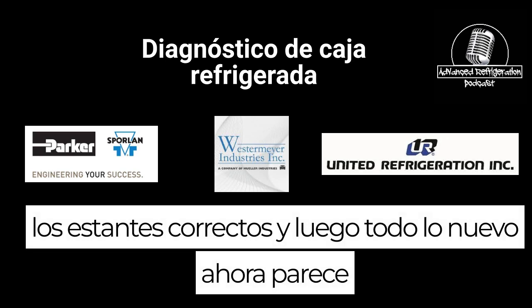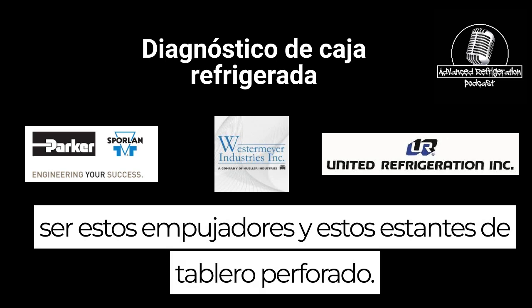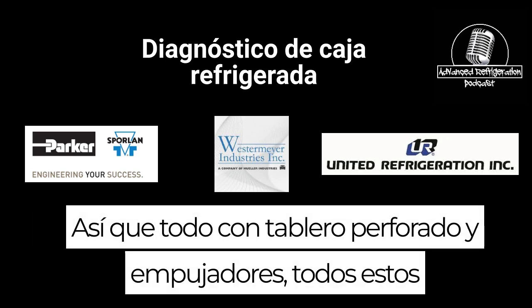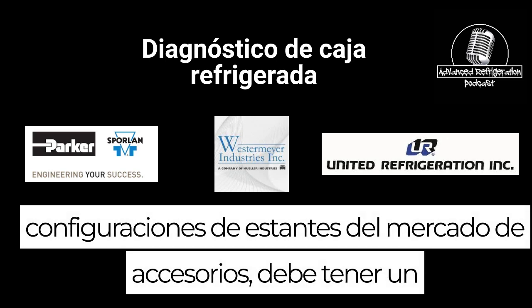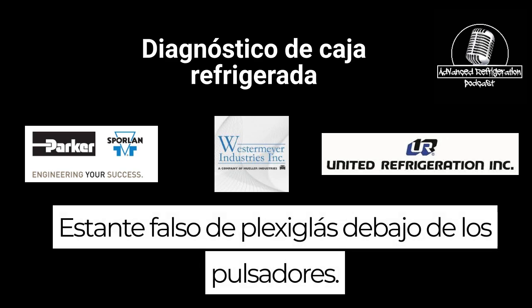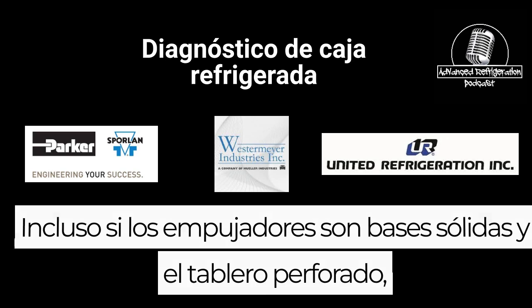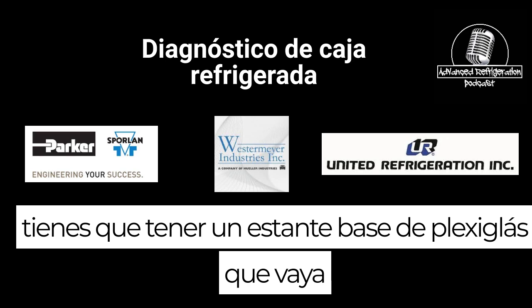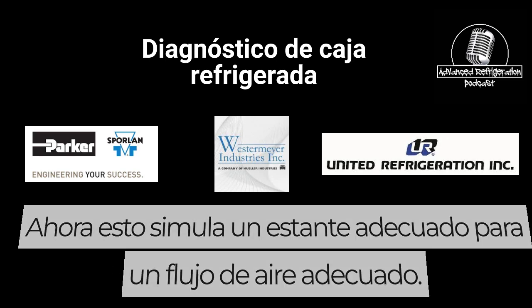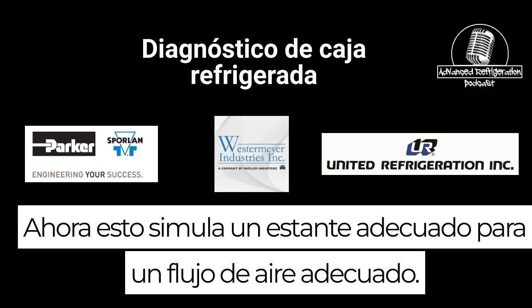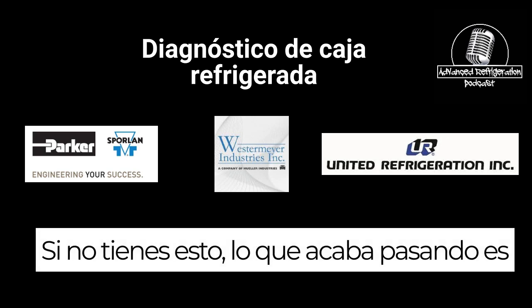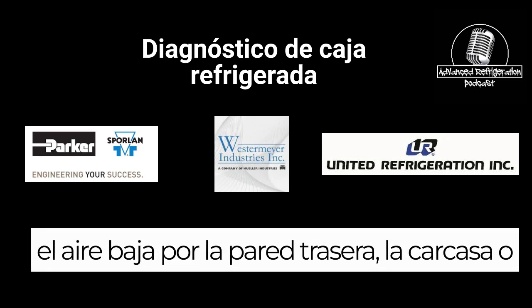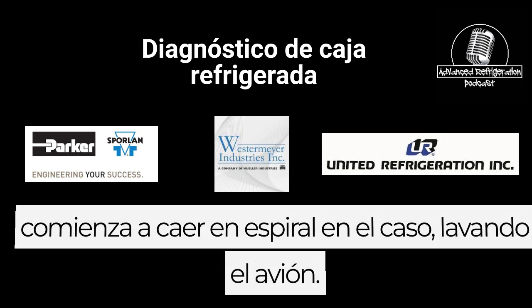And then everything new now seems to be these pushers and these pegboard shelves. So with everything with pegboard and pushers, all these aftermarket shelf setups, you have to have a plexiglass fake shelf underneath the pushers. Even if the pushers are solid bases and the pegboard, you have to have a plexiglass fake shelf that goes all the way to the back wall of the case. Now, this simulates a proper shelf for proper airflow. If you do not have this, what ends up happening is the air flows down the back wall of the case, or it starts spiraling into the case and ends up washing out the air curtain.